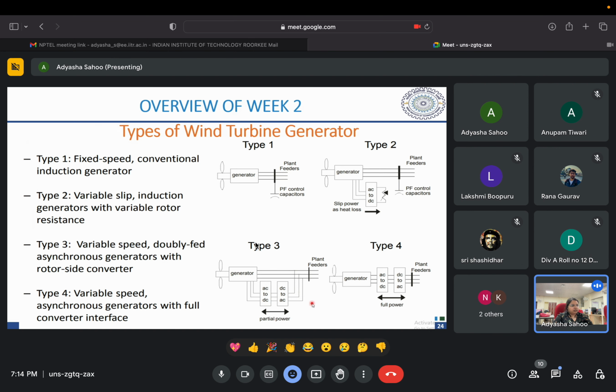That was the DFIG system. In type 4, we have the permanent magnet synchronous generator, or PMSG. Instead of going back in a loop, we have directly a converter in between the machine and the grid, for power correction.